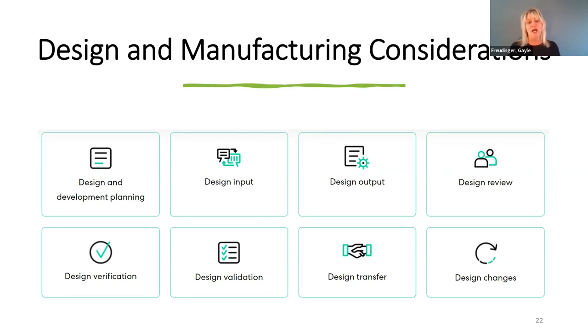But the design control guideline is a quality system approach that covers the entire life of a medical device, starting from the design, production, distribution, use, maintenance, and obsolescence. Design and manufacturing considerations should include all the steps in the process. So you've got your planning, input, output, review, verification, validation, transfer, and then design changes. And really, this could be a separate presentation in itself, just the design and manufacturing considerations.